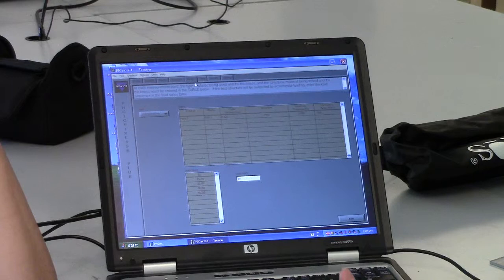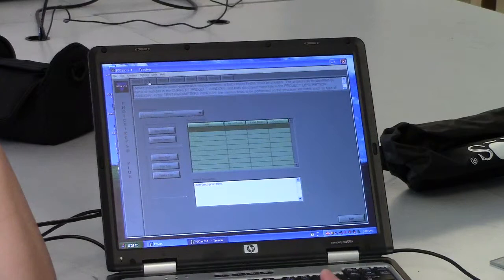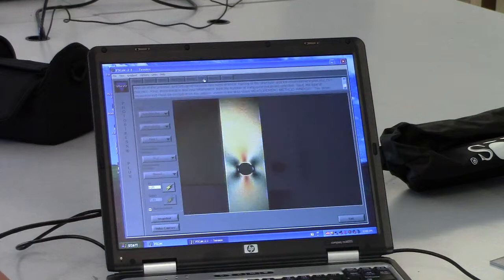Oh, by the way, there's a drop-down box here. There will only be one value there. If you are curious, back in the project, when you have the project for tension, you can create several different tests. So in a single project, you can have multiple tests. We're just running one test. And in that test, we're looking at one point, and we're measuring at four different load values. So back to the points, just to reiterate, we've got our four loads that we're going to do. And now we're ready to test.